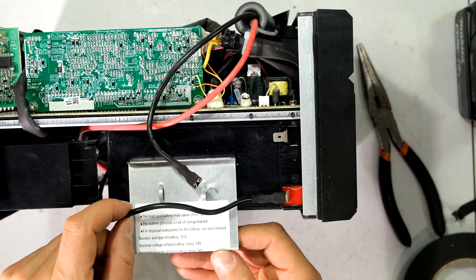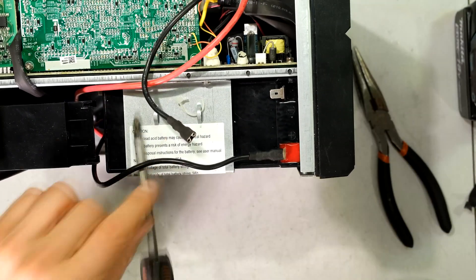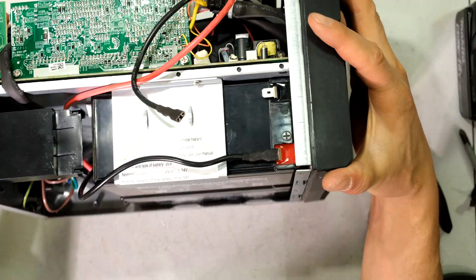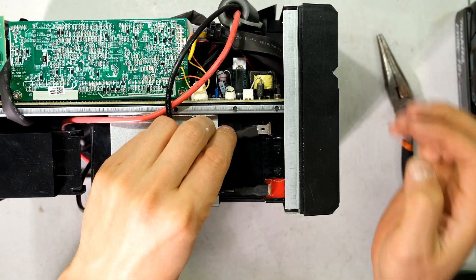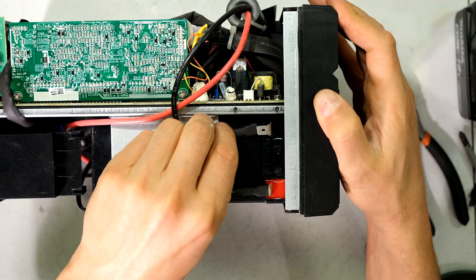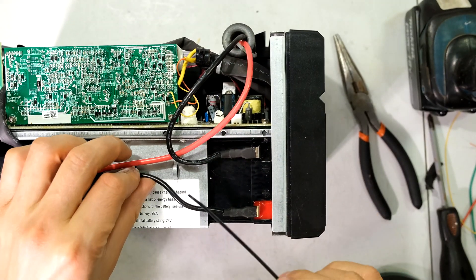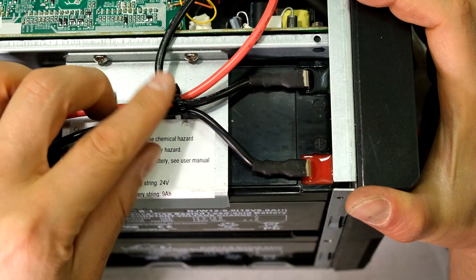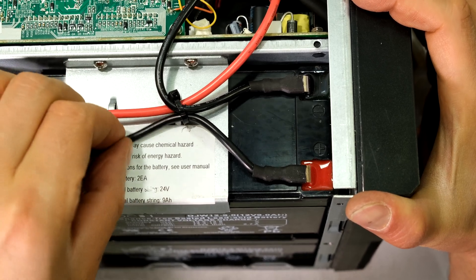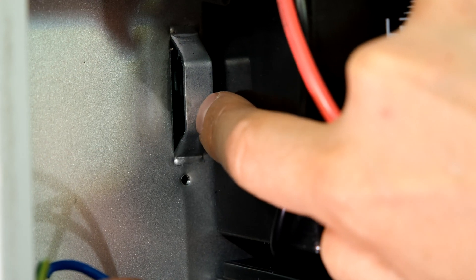At this point I recommend installing the plate first, so I'm installing the plate first. The battery is now securely placed. Now I can connect the negative to this terminal — keep in mind it may spark; don't get a fright if it makes an arc sound. In this case there was no spark. I depress the connector onto the terminal, then tie these wires as they were. I've looped a cable tie around the wires — notice it's not very tight, the wires can still move. Check your connections are all tight and make sure each battery is seated correctly and unable to move.